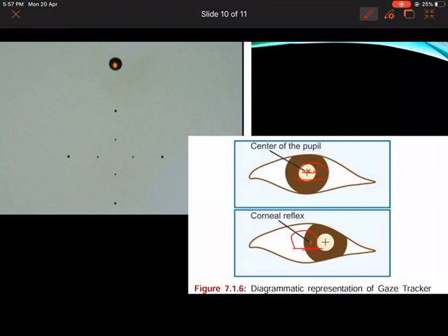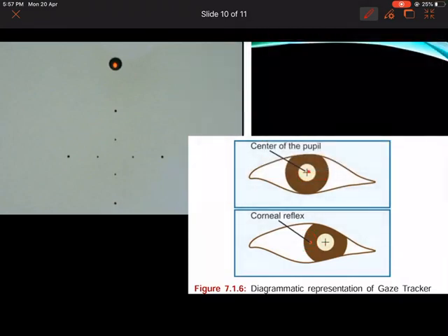If there is a fixation loss, or if the patient moves here and there, this will move from side to side. Earlier the point was here. If the patient moves, it is moved. This is the most accurate, more than Heijl-Krakau, because even the slightest 1 degree movement of the eye can be detected by this.